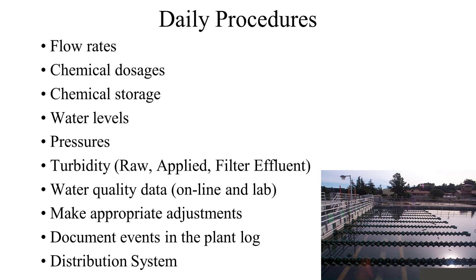Suspended solids can harbor disease-causing organisms, and removing these solids is very important. In addition to turbidity, an operator also has to monitor the chlorine residual, pH, fluoride, temperatures, and other water quality aspects. This data comes from online instruments and from the tests the operators perform in the plant laboratory during the shift.